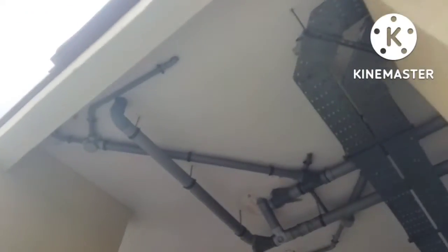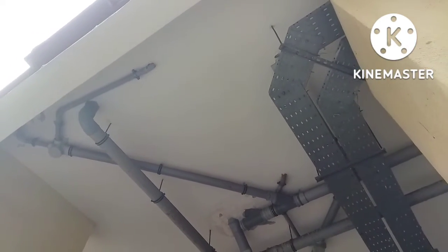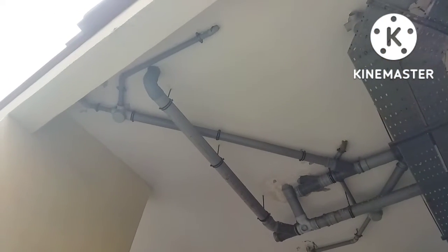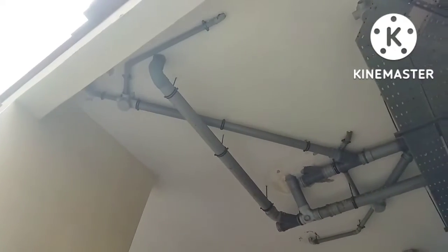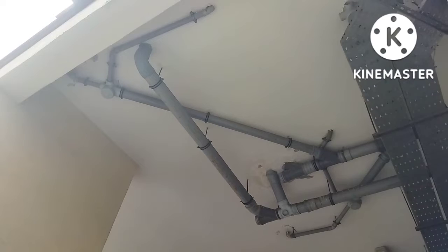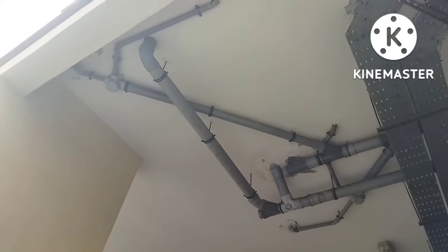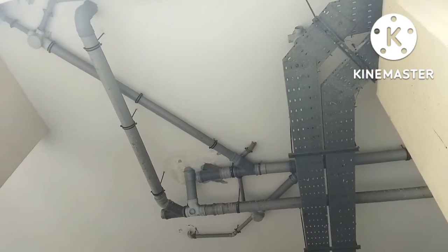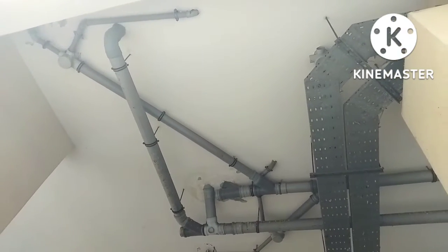Here see the toilets, there is a floor drain, floor trap, having a connection of the wash basin and the main drain. Thereafter there is a soil pipe connection coming directly from the water closet, which will be 110 dia, and for the waste pipe, which is the floor trap connection, it will be 75. These are connecting. See, there is an eccentric reducer as well and a Y fitting. You can find how the connection has been done.